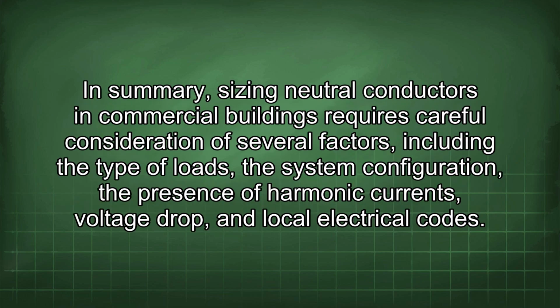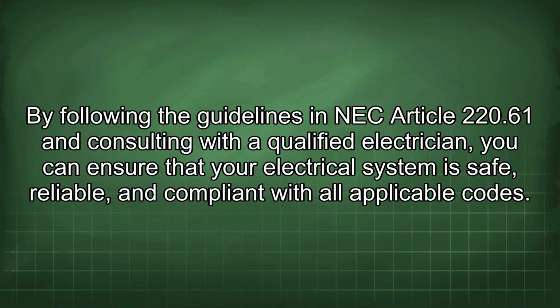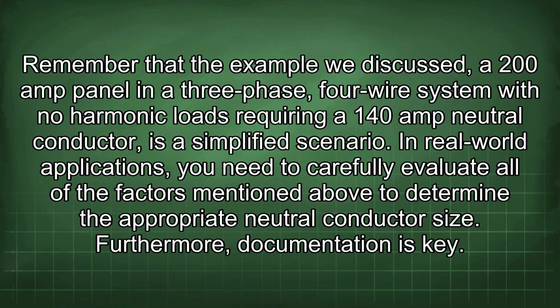In summary, sizing neutral conductors in commercial buildings requires careful consideration of several factors, including the type of loads, the system configuration, the presence of harmonic currents, voltage drop, and local electrical codes. By following the guidelines in NEC Article 220.61 and consulting with a qualified electrician, you can ensure that your electrical system is safe, reliable, and compliant with all applicable codes. Remember that the example we discussed, a 200 amp panel in a 3-phase, 4-wire system with no harmonic loads requiring a 140 amp neutral conductor, is a simplified scenario.